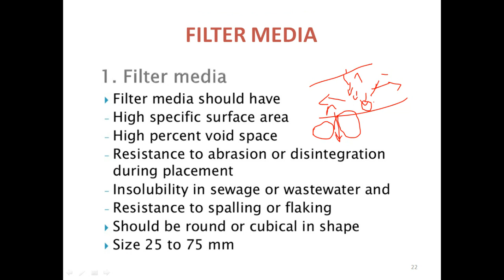Insolubility in the sewage wastewater: whatever wastewater comes from the spray nozzles onto your trickling filter, the filter material should not be soluble in it. It should have resistance to spalling and flaking. Flaking means it should not break in parts or be crushed. Spalling means it should not move from its place; it should stay integrated in place during placement. It should not be abrasive, that is, it should not wear. And the size should be 25 to 75 mm.